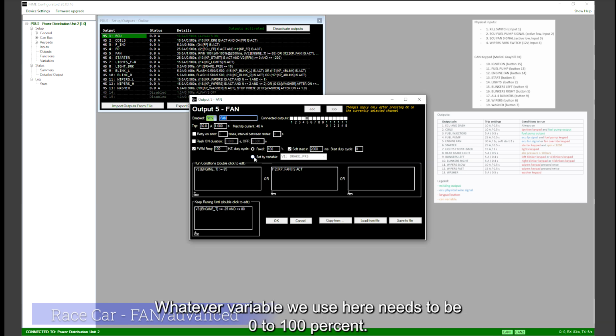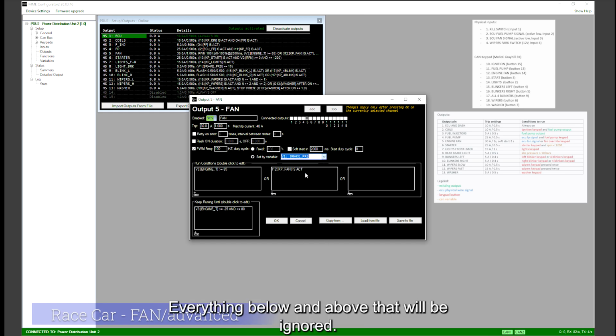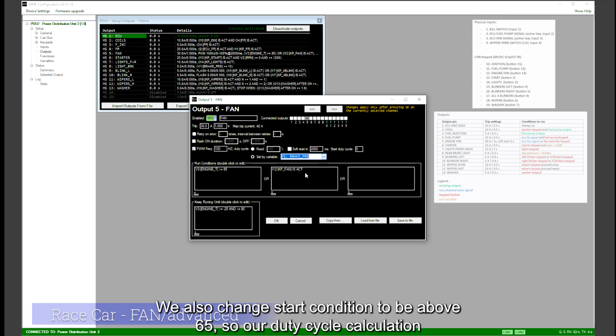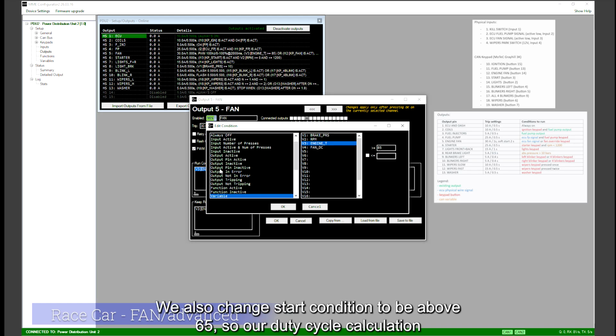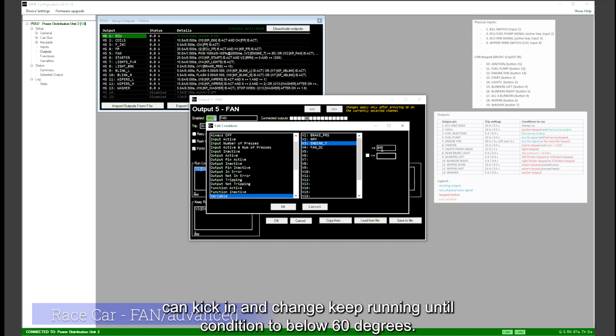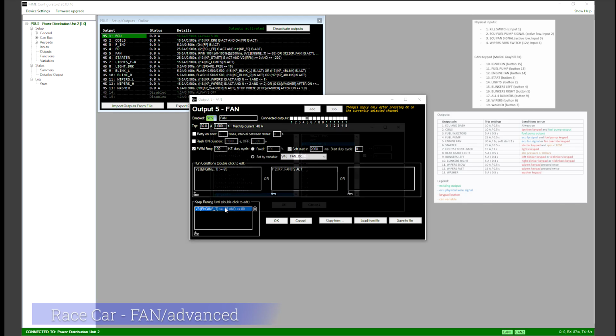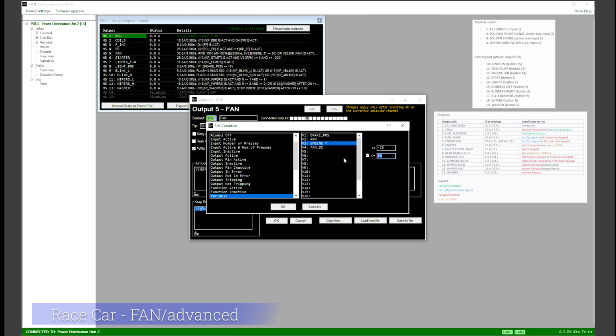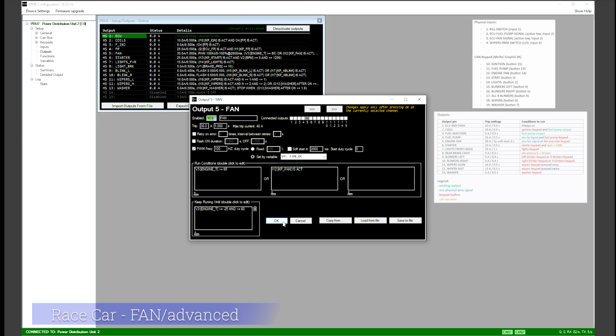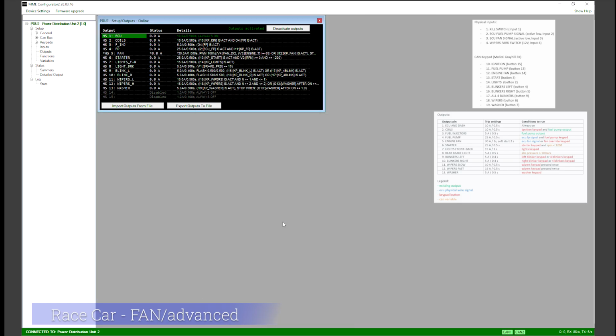Whatever variable we use here needs to be 0 to 100%. Everything below and above that will be ignored. We also change start condition to be above 65, so our duty cycle calculation can kick in and change keep running until condition to below 60 degrees. There you go. We finished setting up our real race car example.